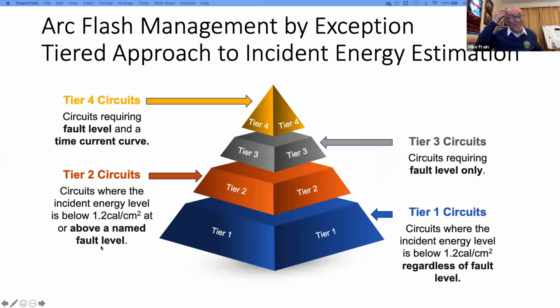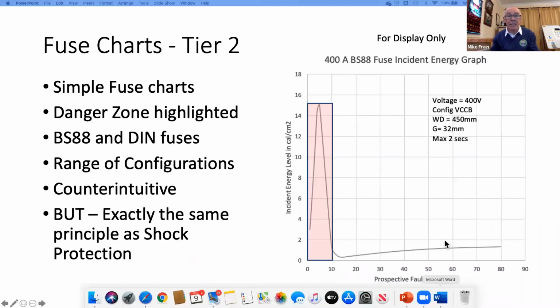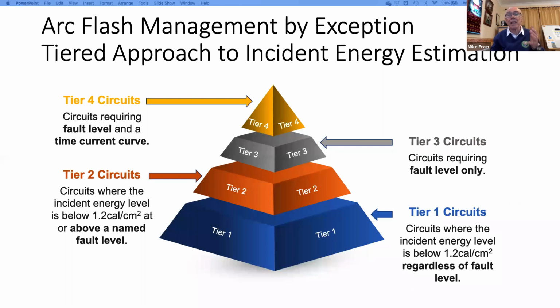And when it comes to working out the parameters for ArcFlash, I've created what I call ArcFlash management by exception, a tiered approach to incident energy estimation. And this is on the understanding that in most industrial and commercial sites, the vast majority of incident energy levels are going to be below 1.2 calories at a working distance, certainly, let's go back to that, a working distance of 450 millimeters or 2 feet or 1 foot 6 inches in imperial measures.